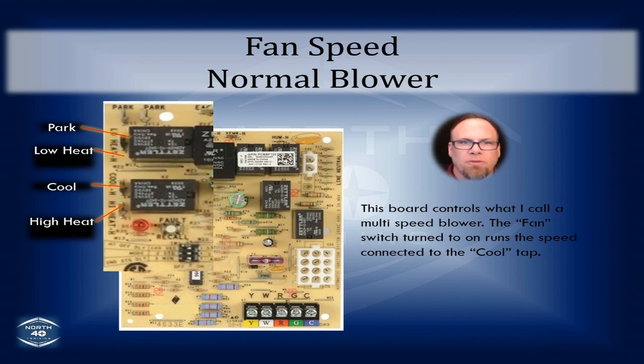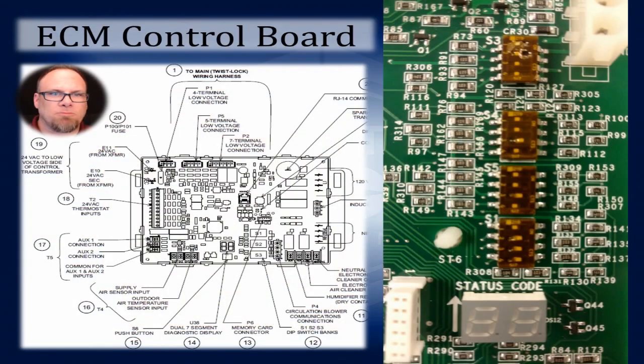Okay, and there's a little bit closer look of what we're talking about. Okay, this one's a little bit different because here we actually have a control board for a more advanced system that has an ECM motor or a variable speed motor. And you can see on the left-hand diagram out of the manufacturer's installation instructions, there's some switch banks there. And ironically, the way that those are labeled is S1, S2, S3, those are switch banks. And they don't necessarily always work out that way.